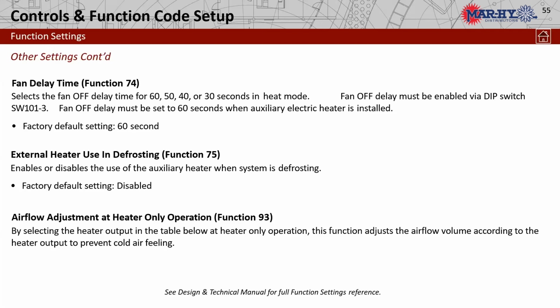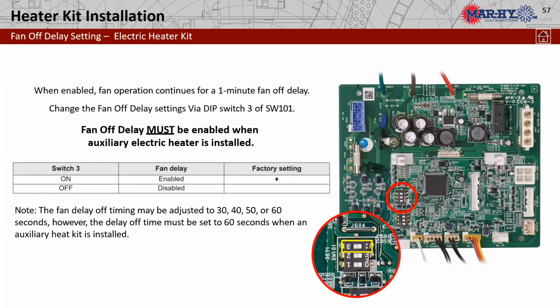Function 93, airflow adjustments. Now what this does, this sets the airflow adjustment based on the strip heat. So depending on what strip heat you got, you're going to set that setting so that it will have enough minimum airflow to facilitate that strip heat, which we will cover. What we're looking at here is when we install them strip heaters, this is where that dip switch is located. There are 2 sets of dip switches on the main PCB of the indoor air handler. And we will go to switch set 101 and flip the switch number 3 to on. There again, that enables us to be able to use the fan off delay.